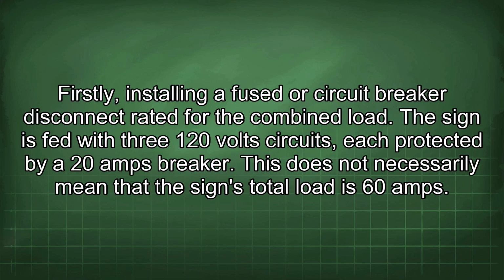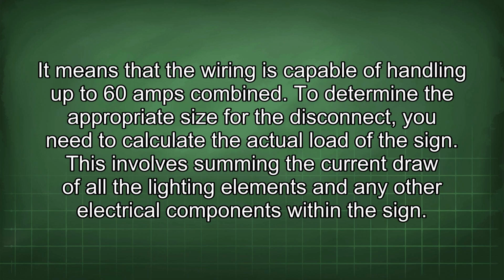Firstly, installing a fused or circuit breaker disconnect rated for the combined load. The sign is fed with 3 120-volt circuits, each protected by a 20 amps breaker. This does not necessarily mean that the sign's total load is 60 amps. It means that the wiring is capable of handling up to 60 amps combined. To determine the appropriate size for the disconnect, you need to calculate the actual load of the sign. This involves summing the current draw of all the lighting elements and any other electrical components within the sign.